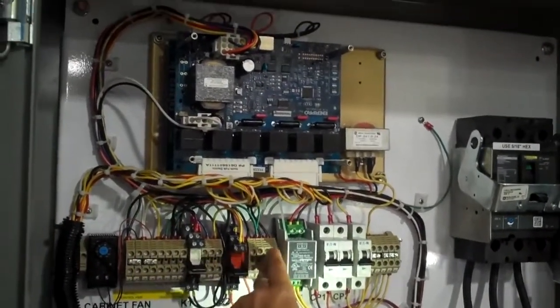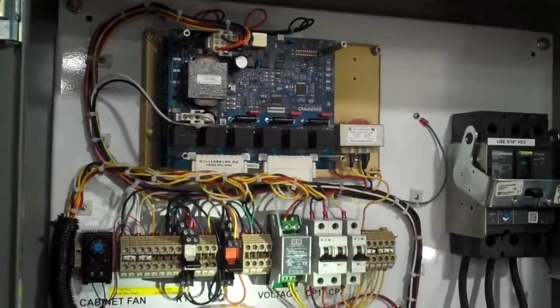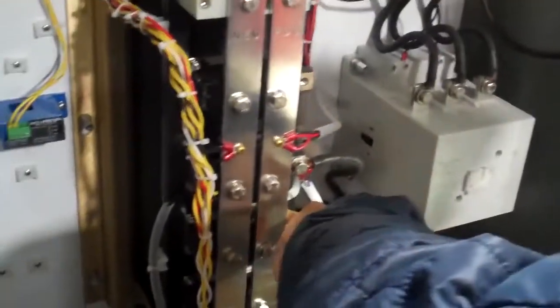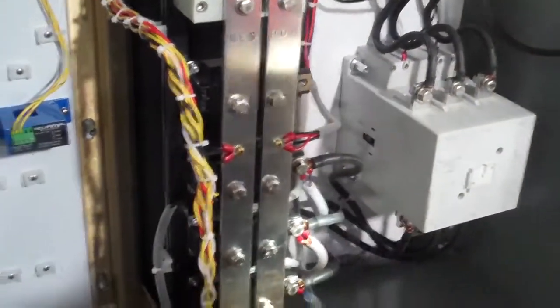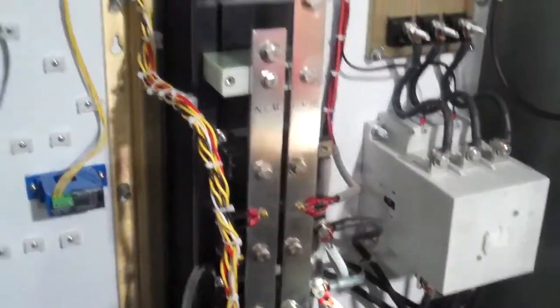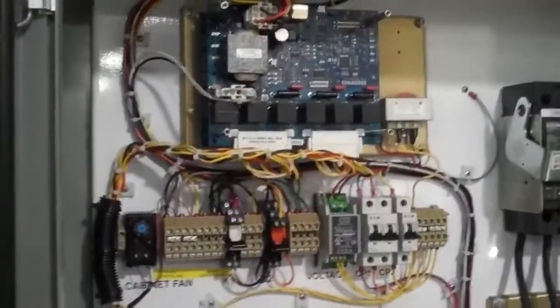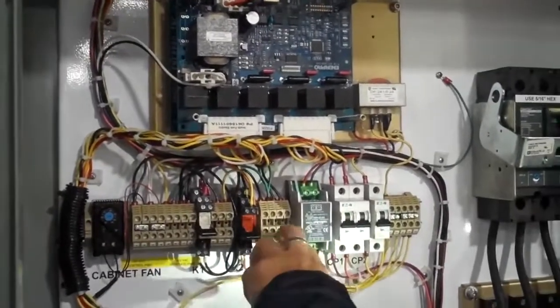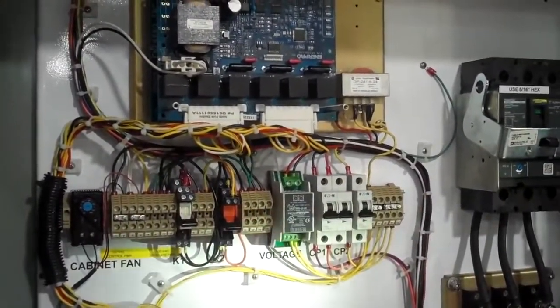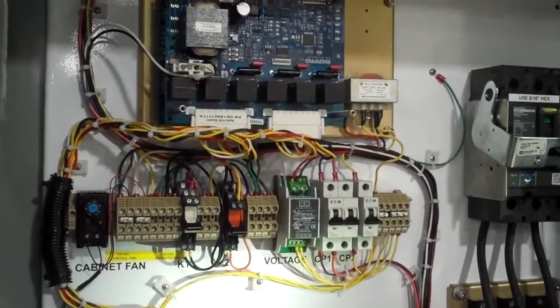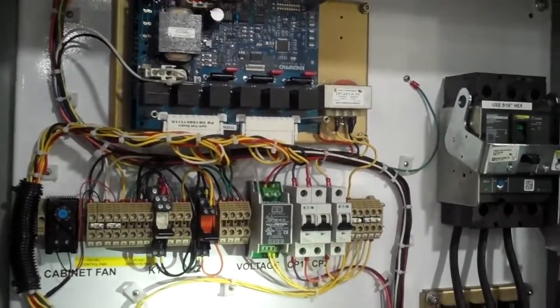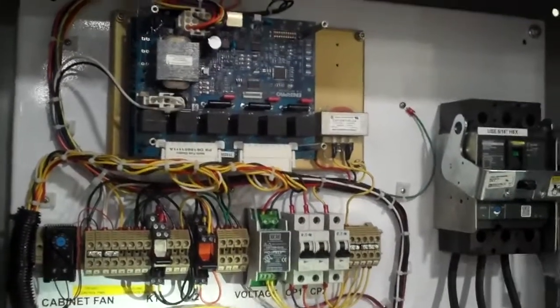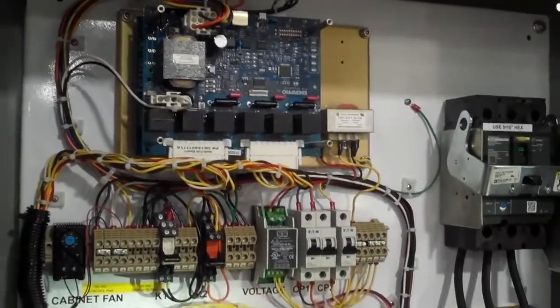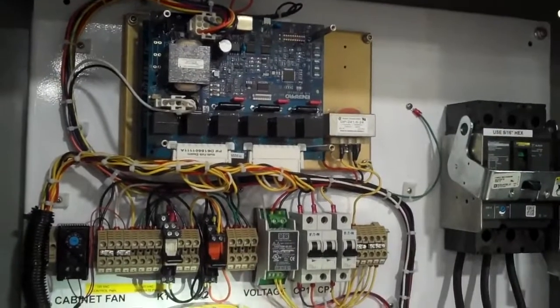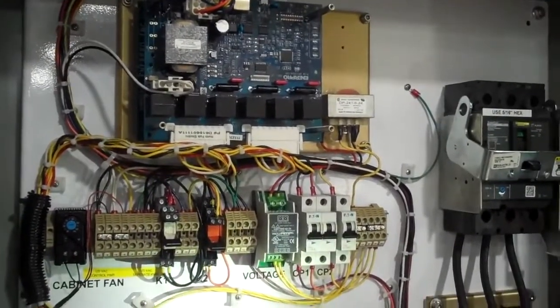Positions 14 and 15 monitor a bimetal temperature disc that is here in the middle of the two hottest SCRs, and it's picking up that hottest spot on the heatsink. That is normally closed, and that dry contact closure will open when the temperature exceeds 93 C. At that point, per the original design, the customer will determine if they are going to maybe command the emergency button to turn it off.